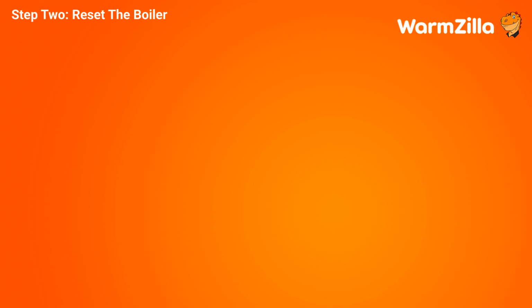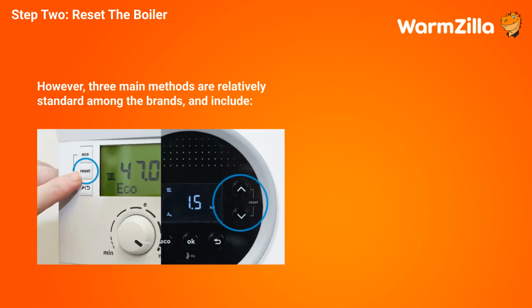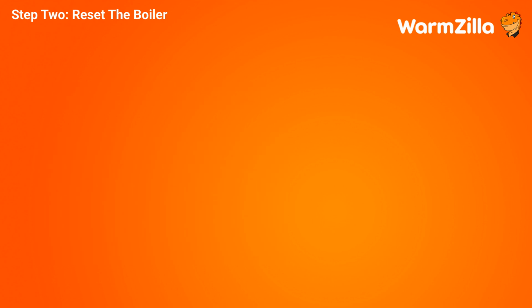Step 2. Reset the boiler. As mentioned, there are numerous methods of resetting Combi boilers. However, three main methods are relatively standard among the brands. Reset button. More common nowadays, Combi boilers will have a dedicated reset button located on the front of the unit. Usually, the process to reset the boiler requires pressing and holding the reset button, marked with a symbol or a flame with a line through it, for about 5 seconds, until the error code clears or the display flashes.